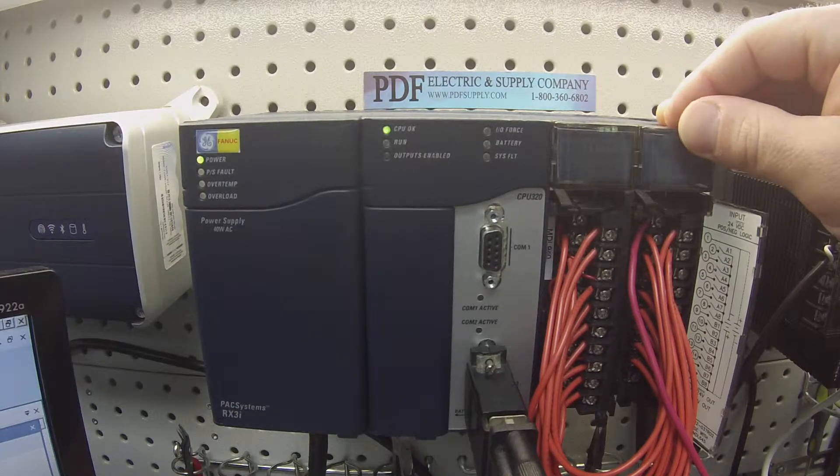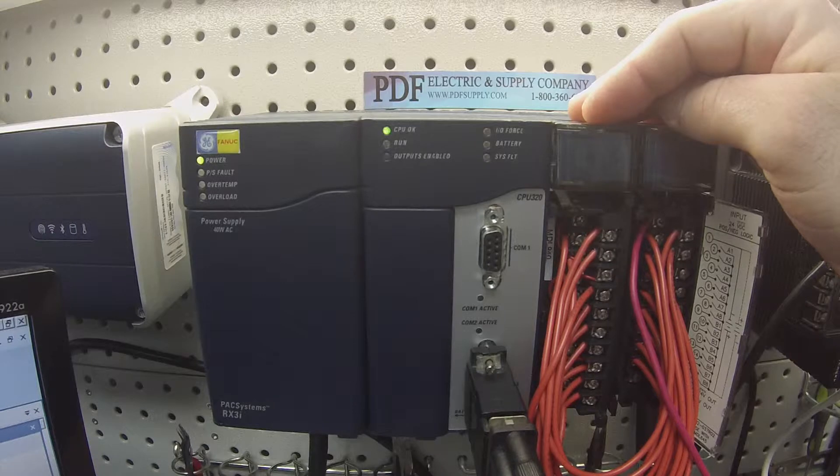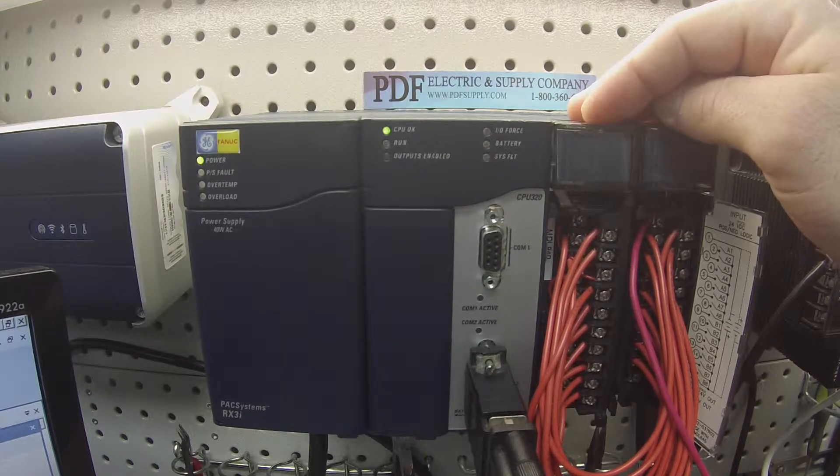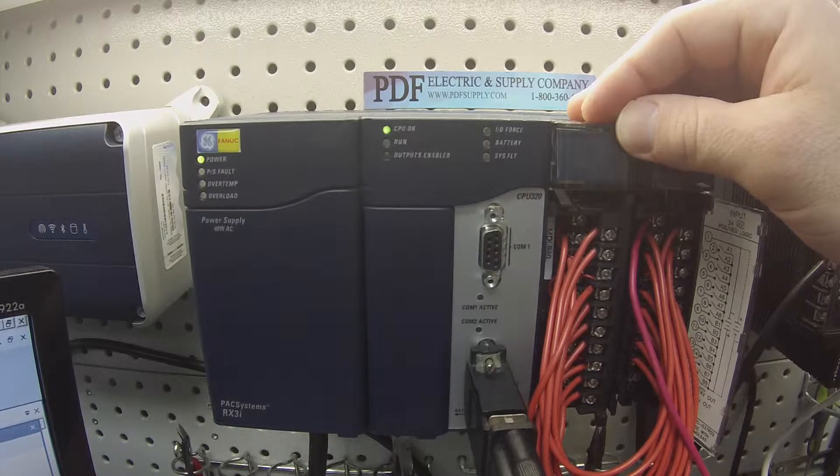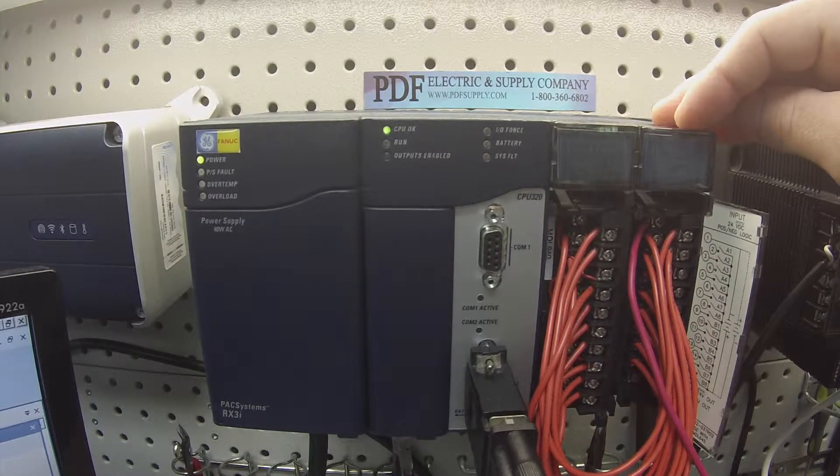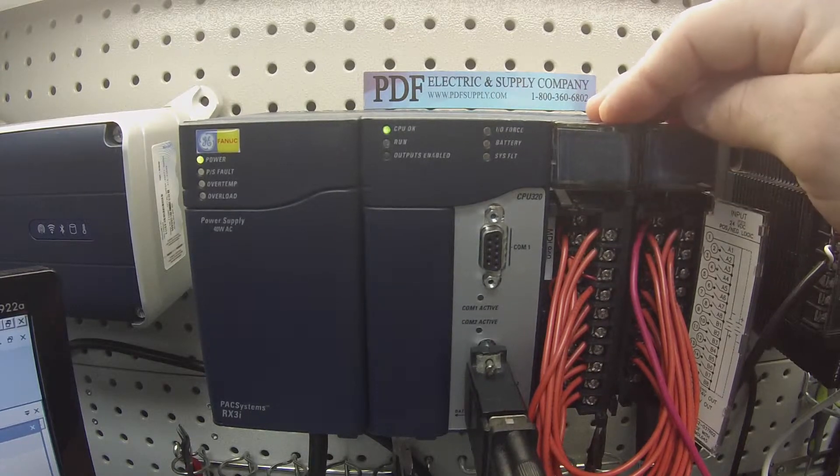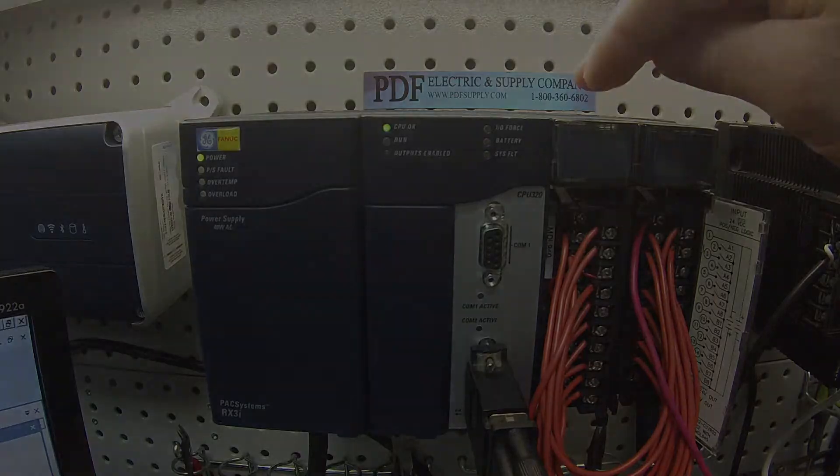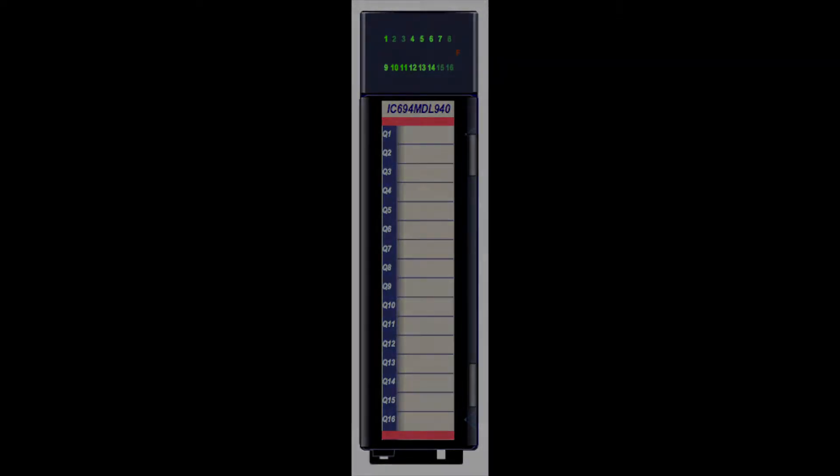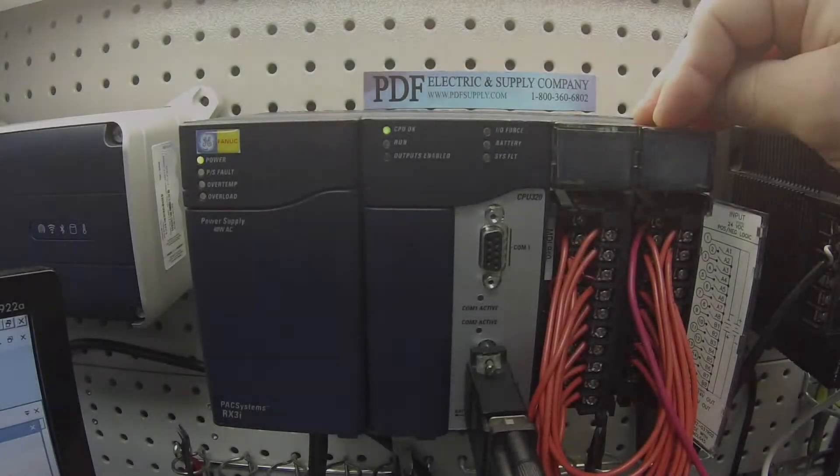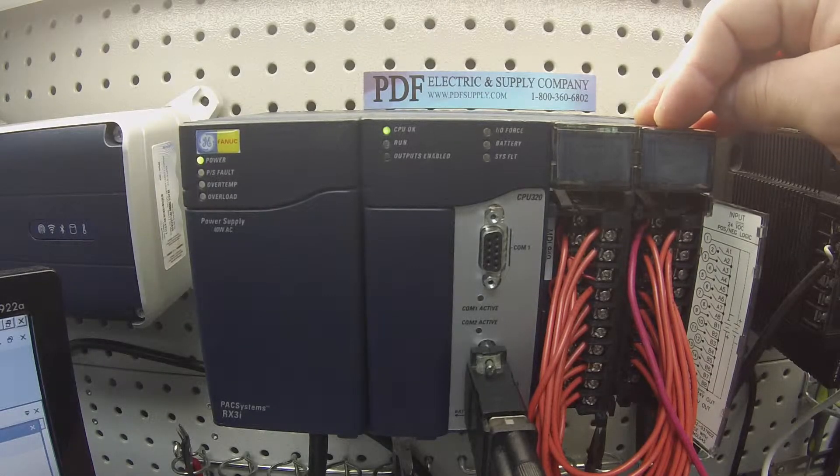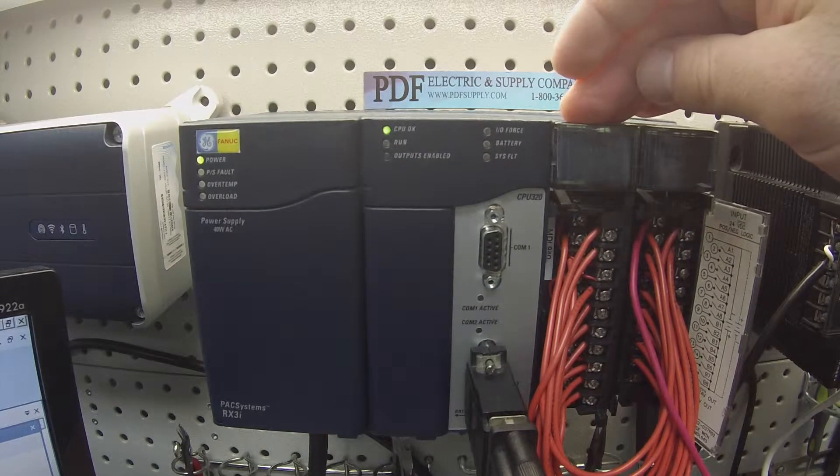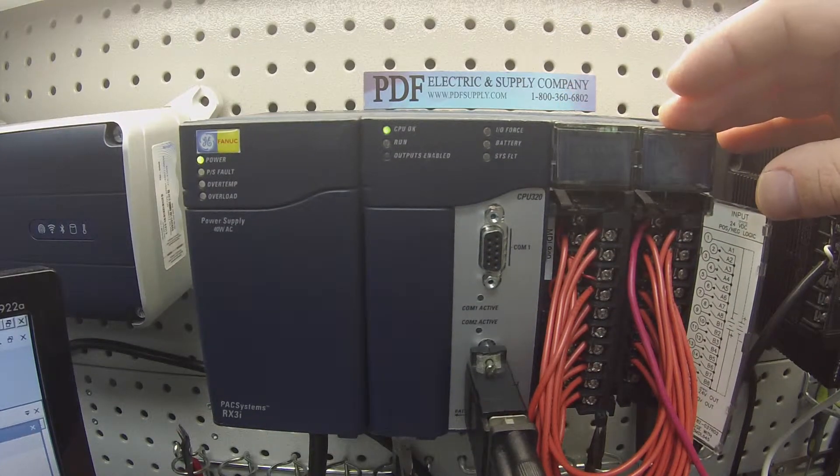The purpose of this test was really for the IC694MDL940 16-point relay output 24 volt DC. If you don't have an MDL645 or 646, I'll give you a quick description on how you can test it without an input. What I've basically done here is I have a 16-point 24 volt DC output feeding its power to an IC694MDL645 or 646 16-point 24 volt DC input. So when I power this and turn a channel on, I should see a channel turn on in the input.